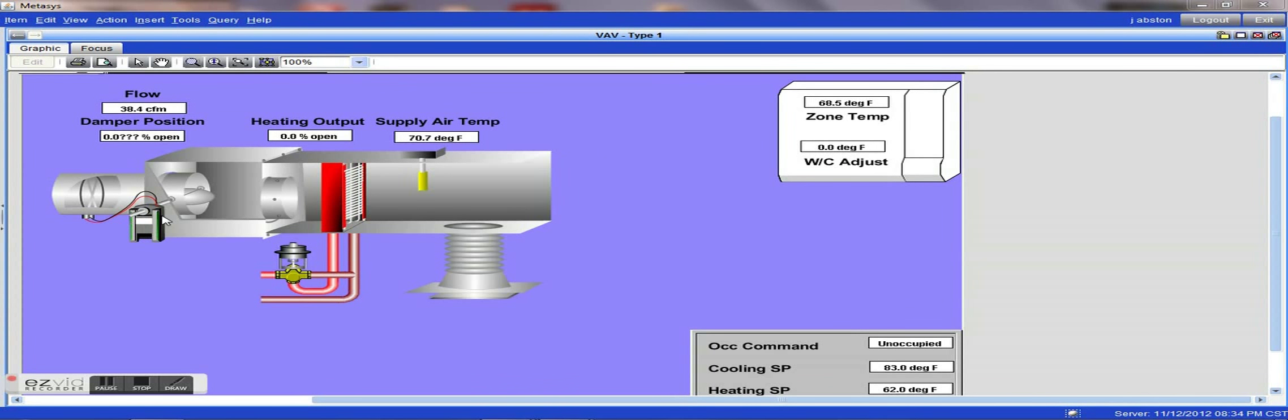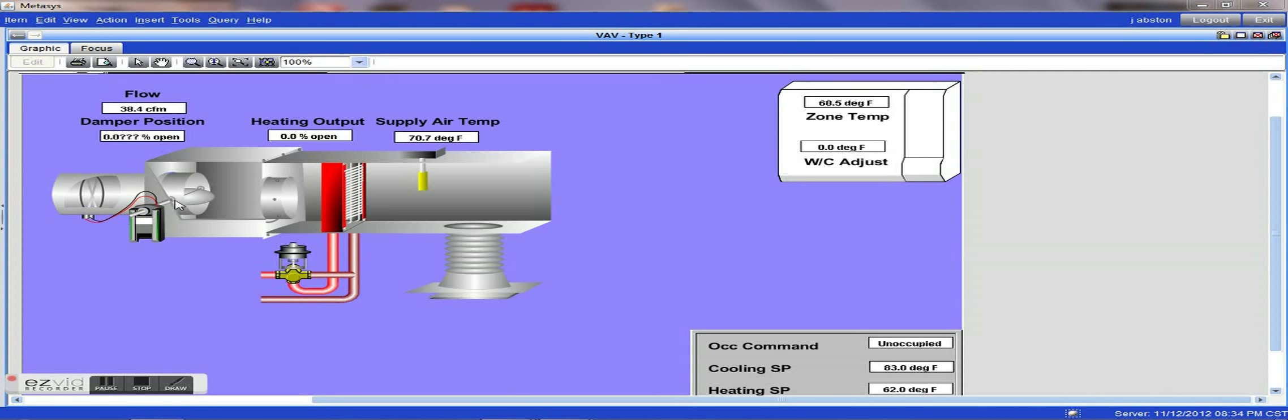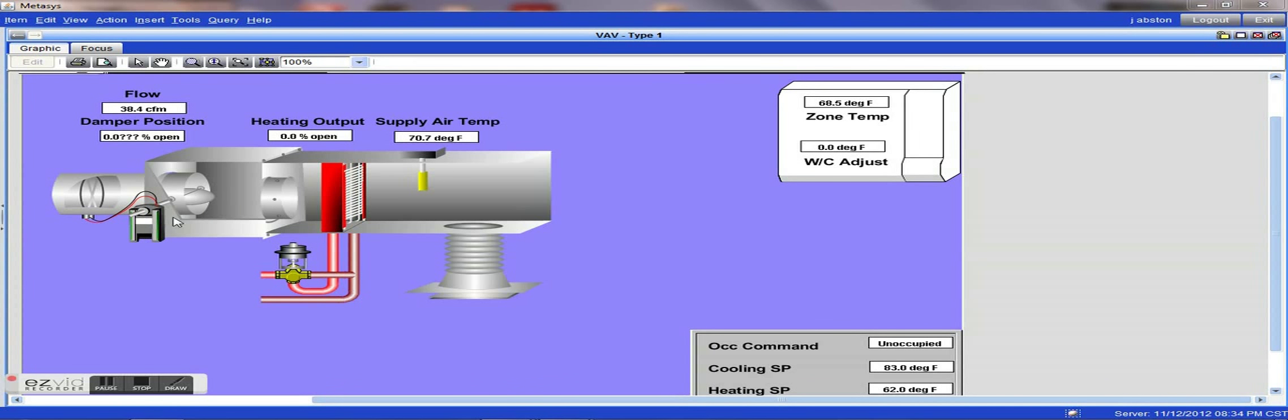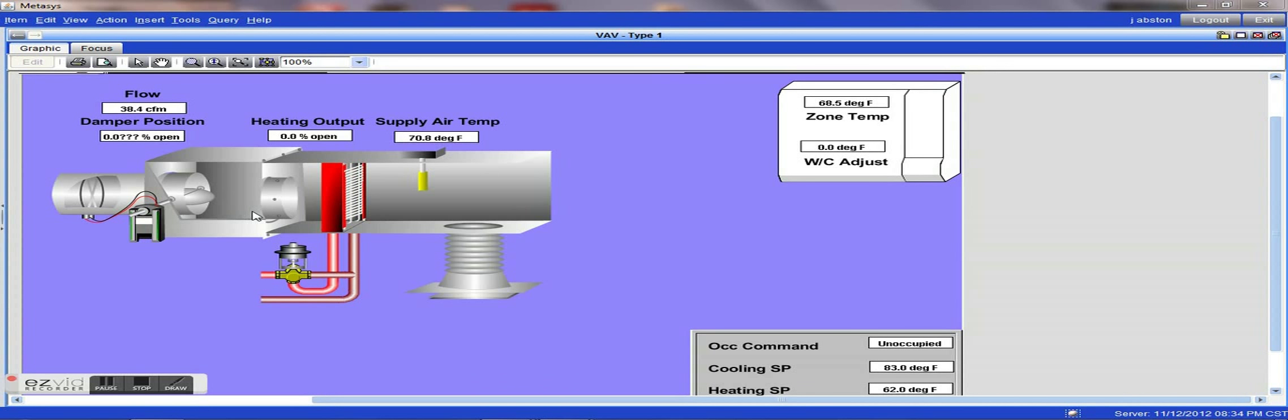This is a small graphic showing a VAV with an integrated damper actuator. This particular unit will measure the air flow coming through the ductwork, calculate what the air flow needs to be based on the programming of the device, which is usually set up by engineering as far as the amount of air flow into a space to adequately heat or cool.